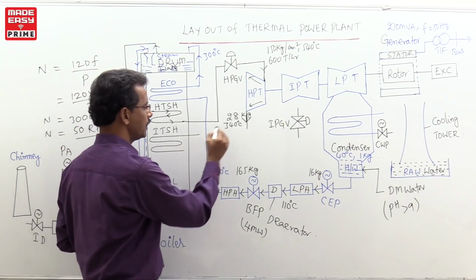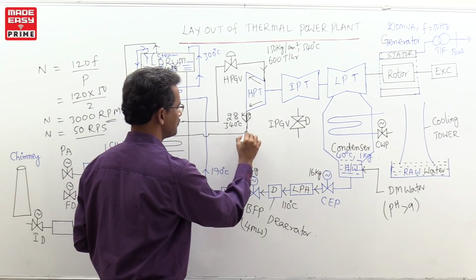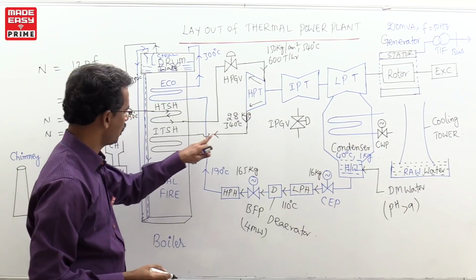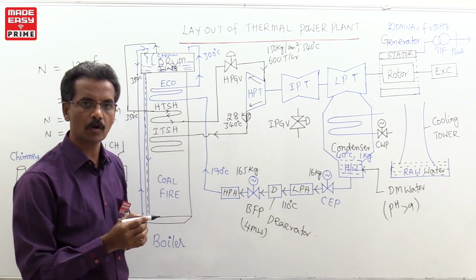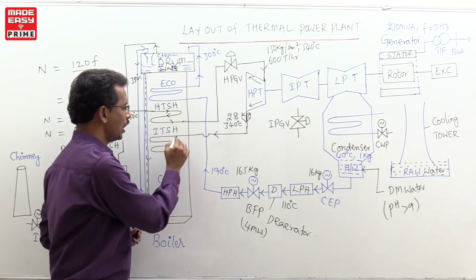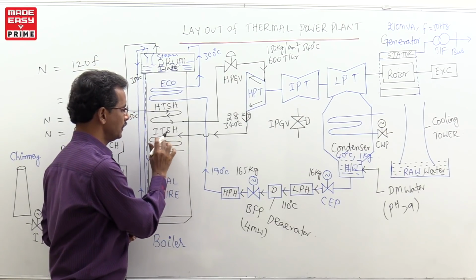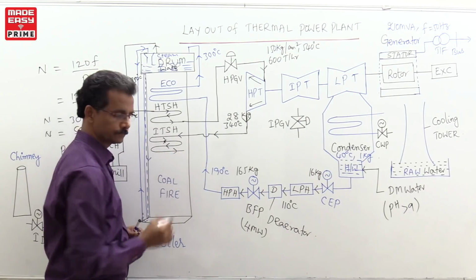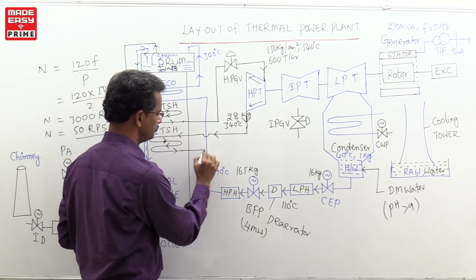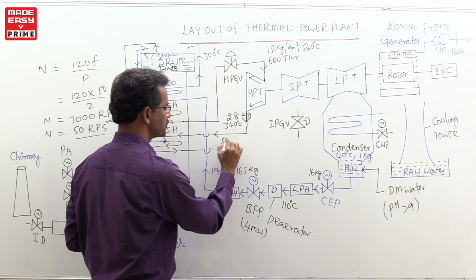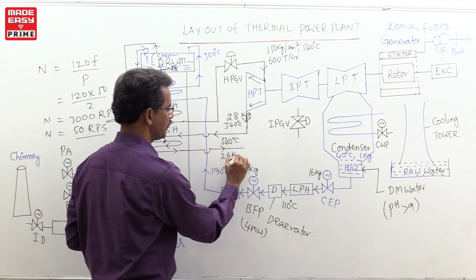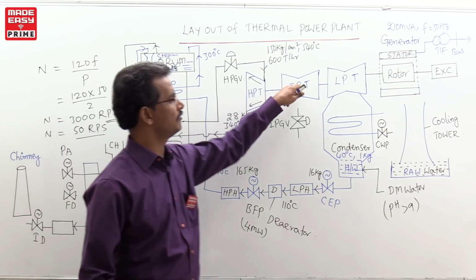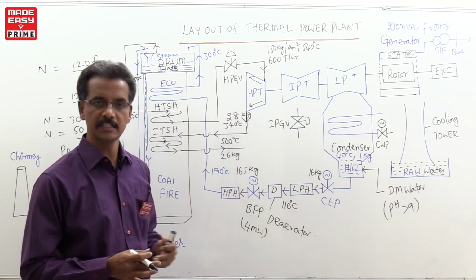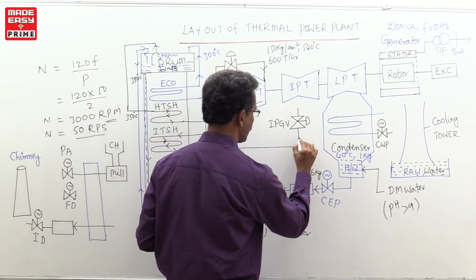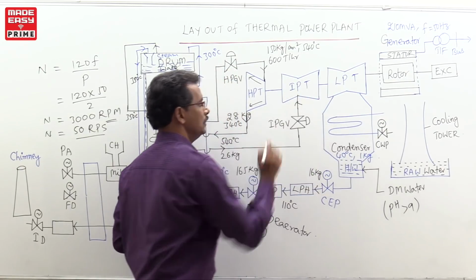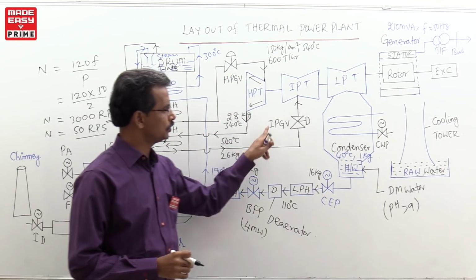So, whatever temperature and pressure is coming out from the HP turbine is passed through the IT superheater, that is, the intermediate temperature superheater. The output of the intermediate temperature superheater is used to improve the parameters of the steam. It will raise the steam temperature to 540 degrees centigrade, but the pressure will drop to 26 kgs because the volume of the IP turbine is much higher than the HP turbine. Right. These parameters enter the intermediate pressure turbine through the IP governing valve.